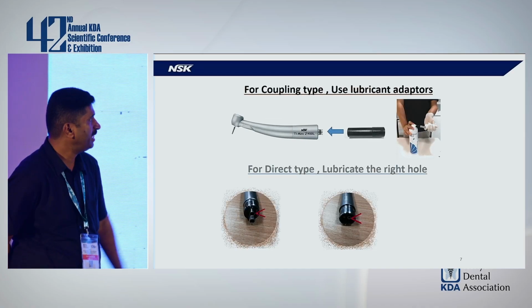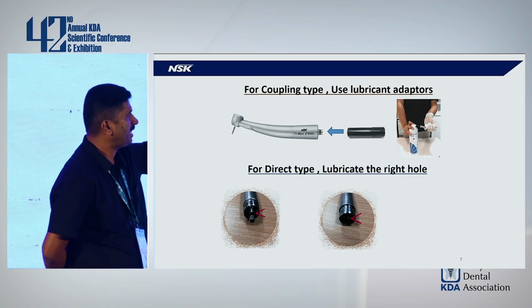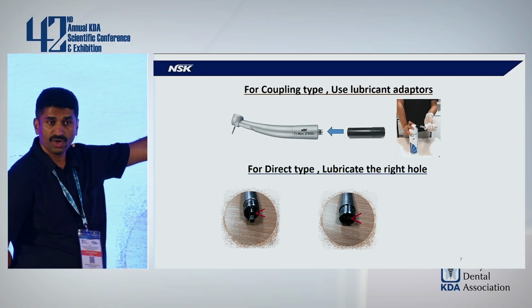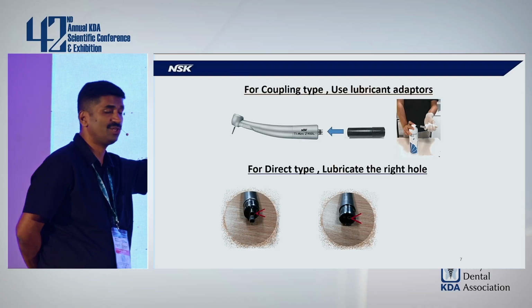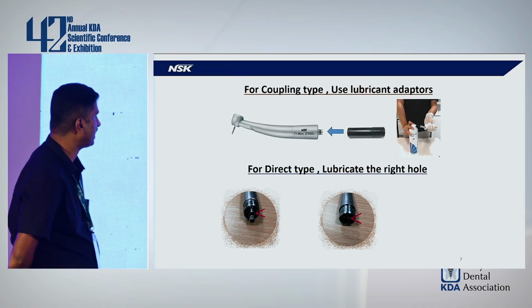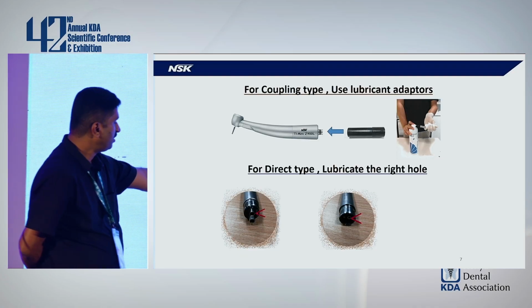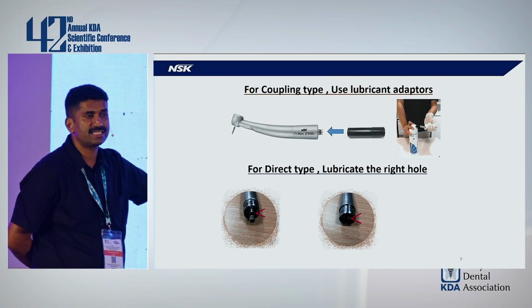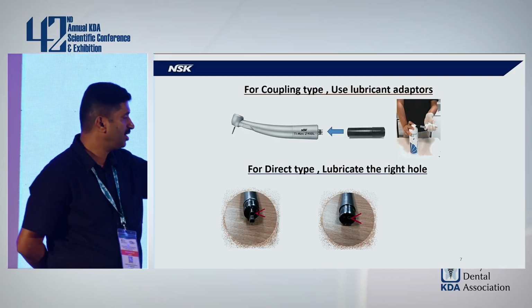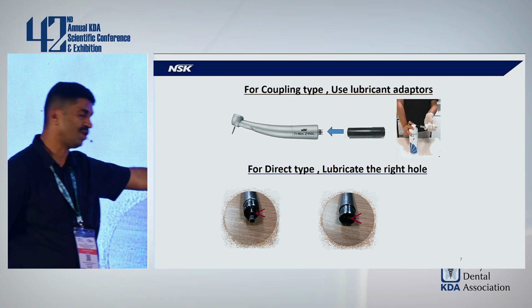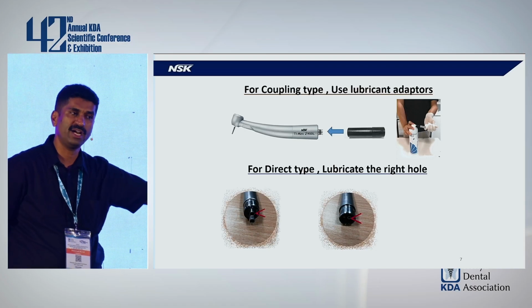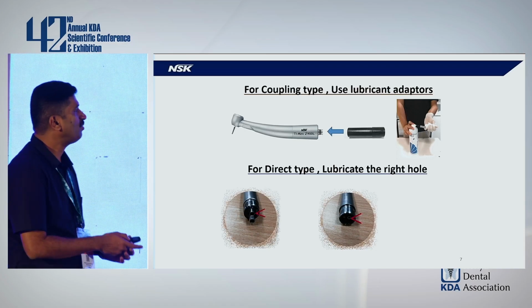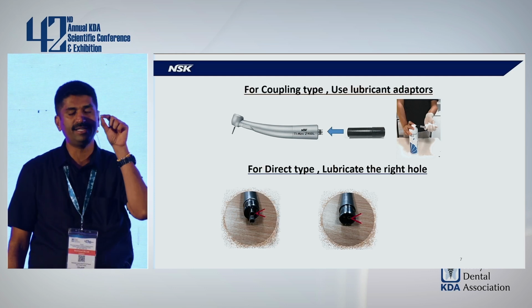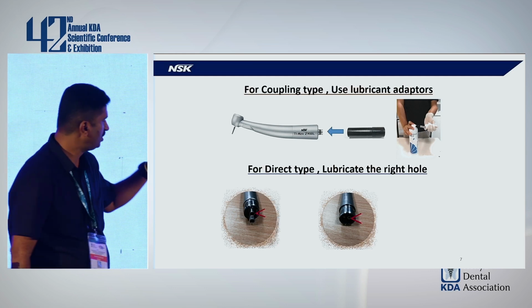Now, how to lubricate? As I said, you just connect the lubricant adapter, mount it on your oil spray first, then bring the handpiece to the oil spray and spray for 3 seconds. If you're using a 4-hole handpiece, the smaller hole should be lubricated. If you're using a 2-hole handpiece, that is Borden 2-hole, you have to lubricate the bigger hole. So generally what we do is we point the tip of the oil spray to the hole of the handpiece.